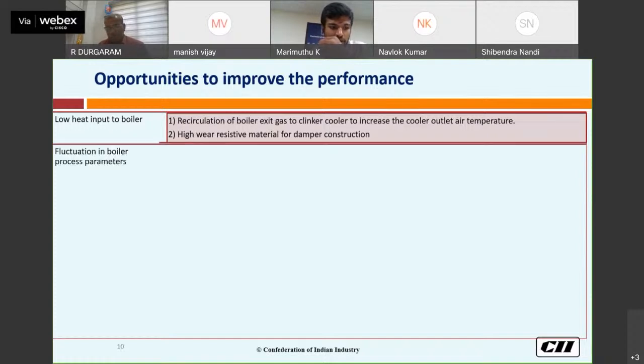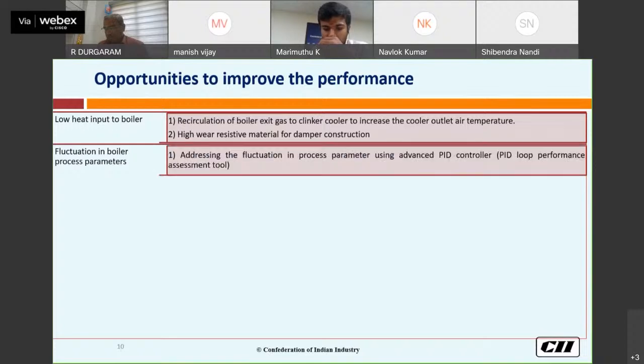So we need to take care of high wear resistant material for damper construction at the design stage. The next one is fluctuation in boiler process parameters. Nowadays technologies have come up with advancements in the PID controller, so addressing the fluctuation in process control using an advanced PID controller will be helpful. A PID loop performance assessment tool is there, which helps in varying the control valve and damper with minimum variation. So this can be done.